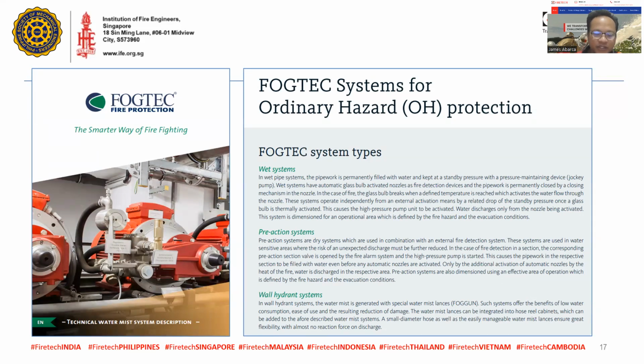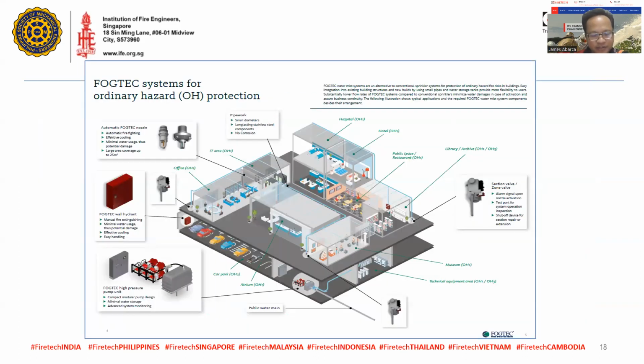Since it's stainless steel, the good thing is it is a solution against corrosion. In your conventional wet system, pre-action, and hydrant, corrosion is one of the big problems encountered, especially when the system has been there for quite a long while. Now, you can see in this image, let's say for ordinary hazard applications such as hospital, hotel, public spaces, library, maybe an IT room, an office, a switchgear room, a museum. Basically, if this is a big building that has different hazards, different applications, or different occupants, you're going to have different systems as well.